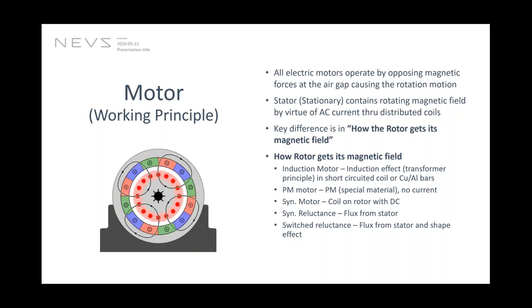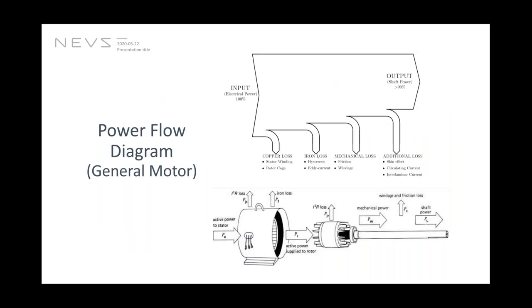So the next step is to explain, this might not be so relevant in this case, but in order to select or determine or make criteria for selection for electrical motors, you need to know where the losses are and how the efficiency works. You cannot simply say that a 90% efficient motor is very good. To have an understanding of the selection criteria, to know where the losses occur is also quite important.